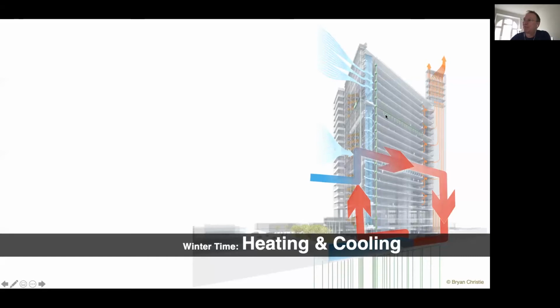We also have piping embedded in the floor slab, which provides radiant heating in wintertime and cooling in summertime. And we have almost 300 boreholes for a geothermal heat exchanger under the building, connected to a heat pump, which lifts this geothermal heat to a useful temperature for the radiant heating and for air heating in the building.